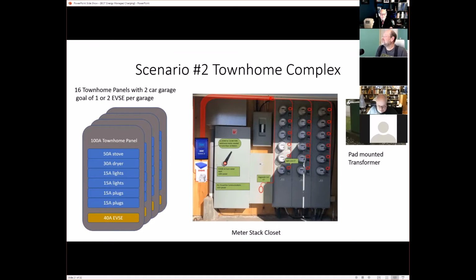They had 3 different pad mounted transformers because they had many buildings on the complex. Each pad mounted transformer would feed a meter stack closet like we see here, with 16 individual meters, one for each homeowner or townhome. Each meter would then feed a 100 amp panel in the townhome's garage.